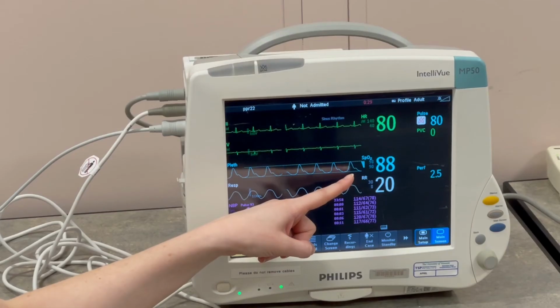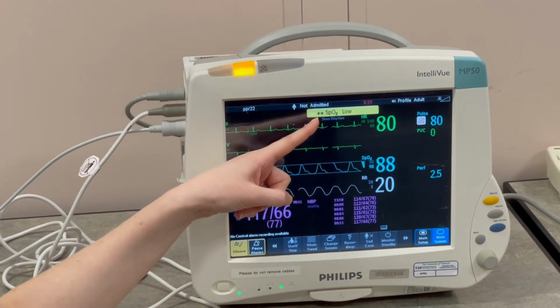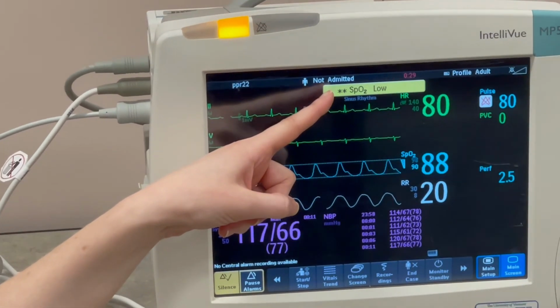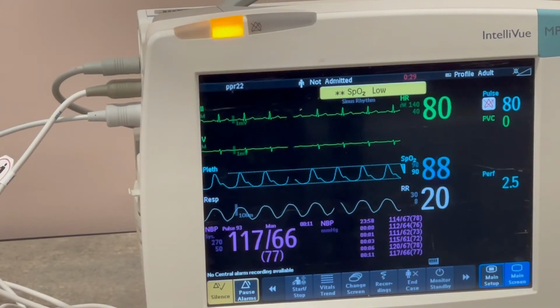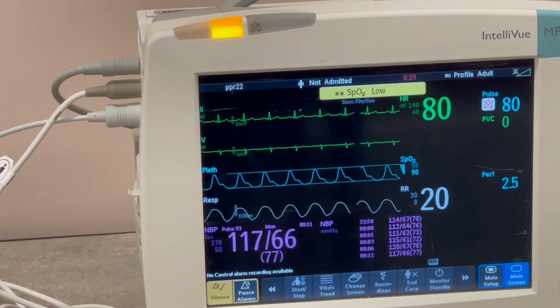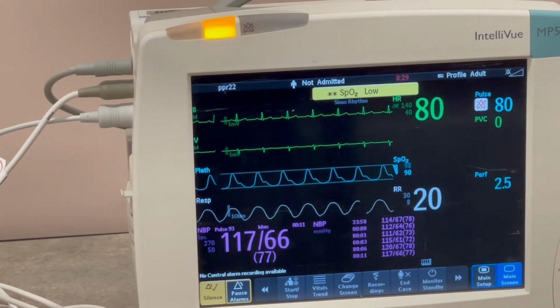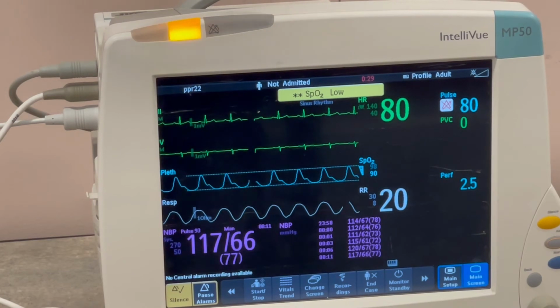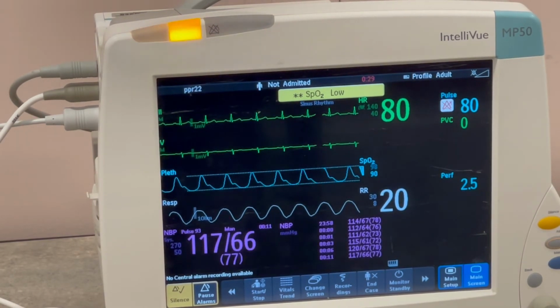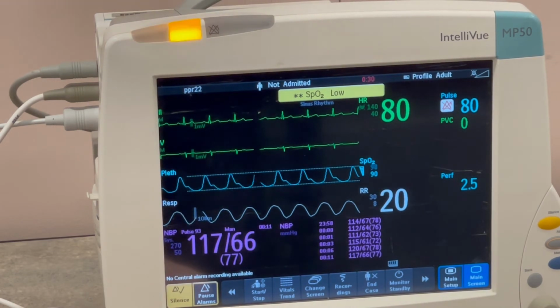Review the manual for how to test the alarms and always follow the manual when it conflicts with these instructions. Not all alarm conditions can be simulated easily. Specific alarms will be included for all clinical parameters, and technical alarms will occur for patient monitor equipment or accessory problems. For all parameters in patient monitors, there will be high and low alarms based on the values measured.